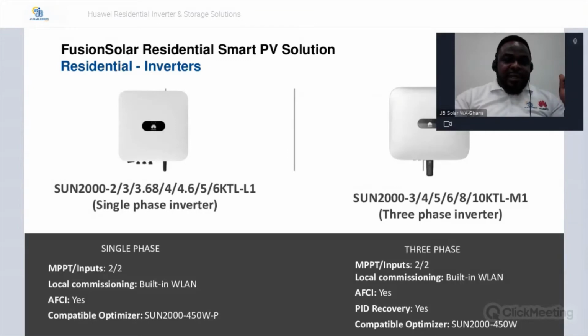You can see it has 2 MPPTs, each MPPT has one input, so for the residential inverters each MPPT has one string per input. For the C&I inverters, each MPPT has 2 strings, so let's not confuse this. For both single phase and three phase residential inverters, each MPPT has only one string. These inverters are also built for high-powered panels, bifacial panels, and floating solar systems, so they're compatible with the most current technology available worldwide.